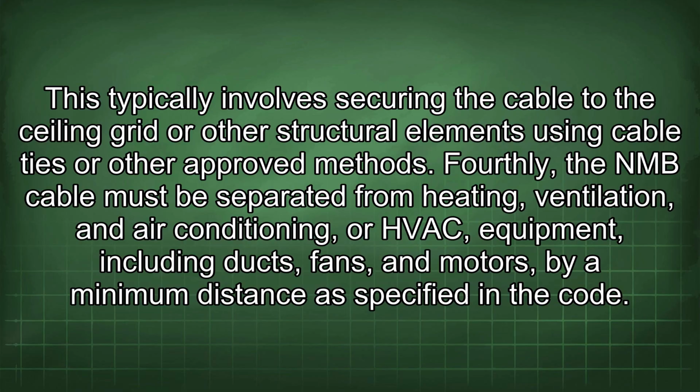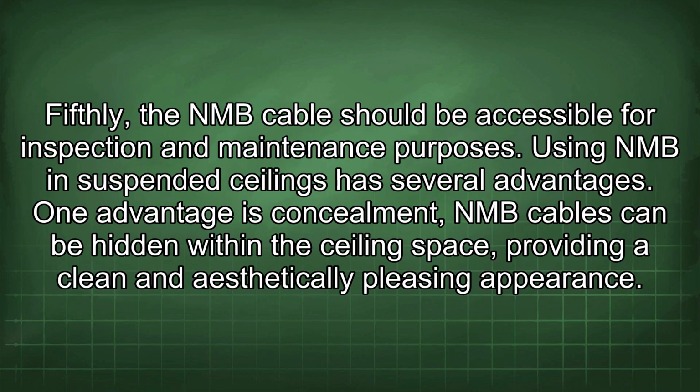methods. Fourthly, the NMB cable must be separated from heating, ventilation, and air conditioning, or HVAC, equipment, including ducts, fans, and motors, by a minimum distance as specified in the code. Fifthly, the NMB cable should be accessible for inspection and maintenance purposes.